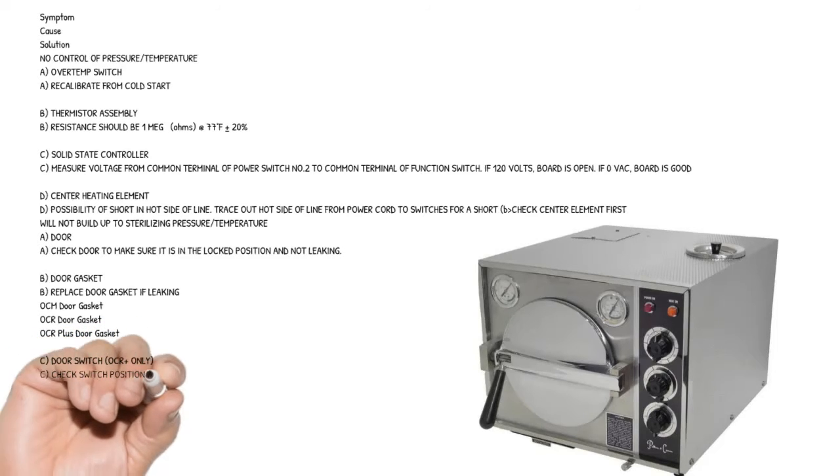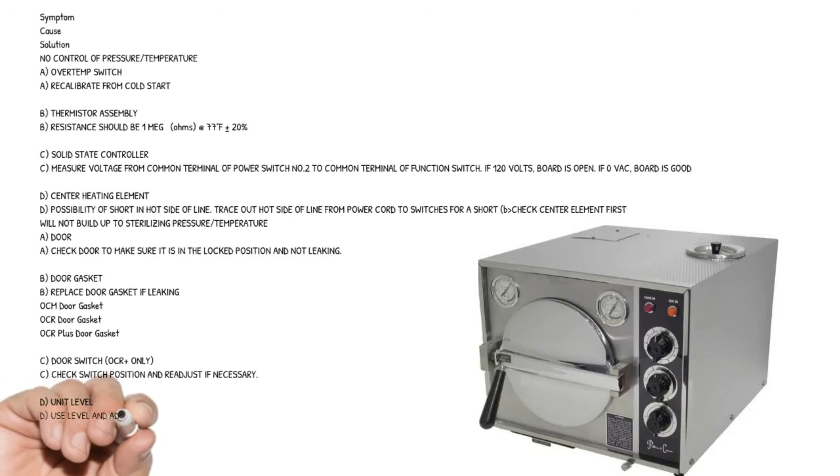Cause C: door switch, OCR plus only - check switch position and readjust if necessary. Cause D: unit level - use level and adjust feet if necessary.